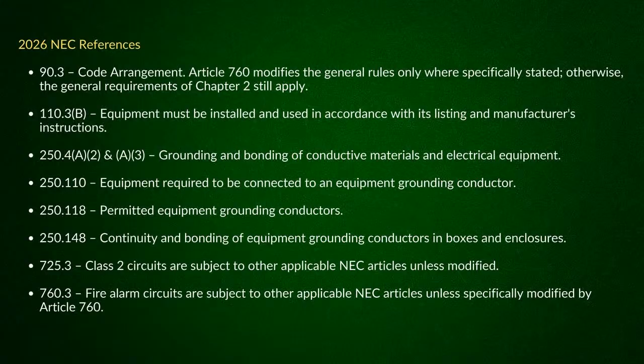And then if you look at 110.3(b), that's where you pick up your listing and labeling and using the manufacturer's instructions. And then when you look at the main general rules, it says over in 250.4(a), 2 and 3, that the grounding and bonding talks about what we just talked about right here.